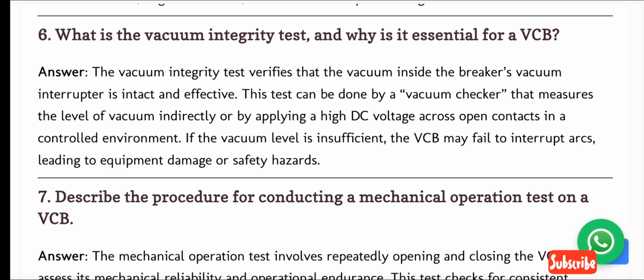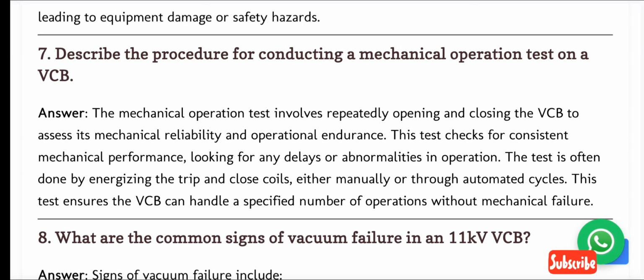Answer. The vacuum integrity test verifies that the vacuum inside the breaker's vacuum interrupter is intact and effective. This test can be done by a vacuum checker that measures the level of vacuum indirectly or by applying a high DC voltage across open contacts in a controlled environment. If the vacuum level is insufficient, the VCB may fail to interrupt arcs, leading to equipment damage or safety hazards. 7. Describe the procedure for conducting a mechanical operation test on a VCB.